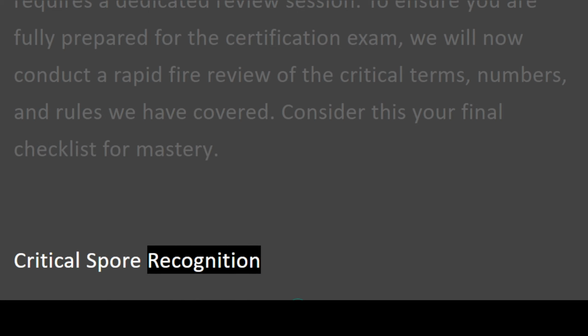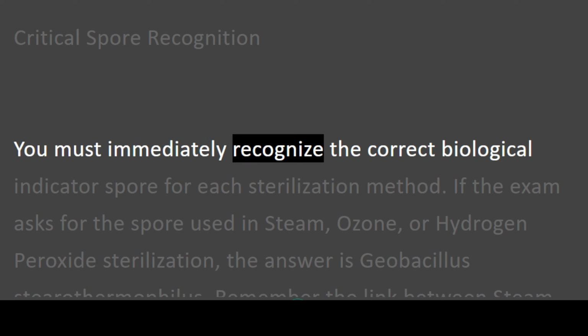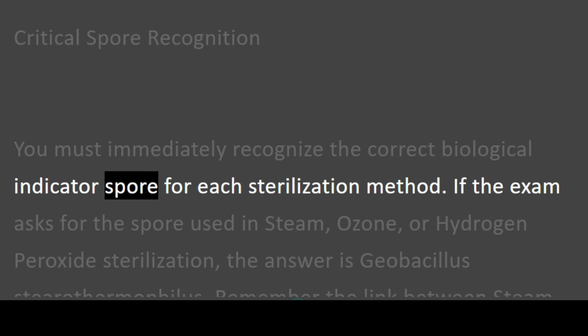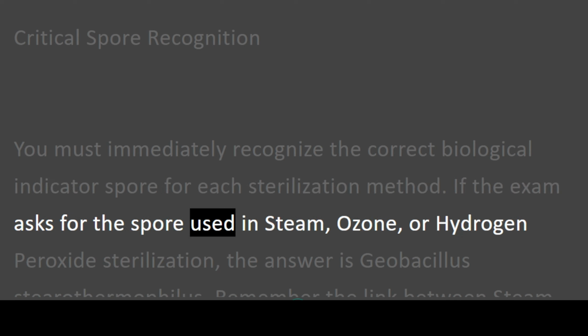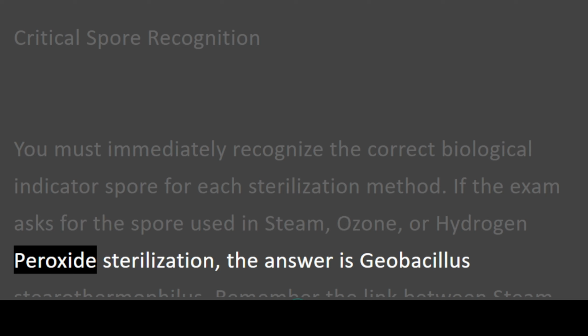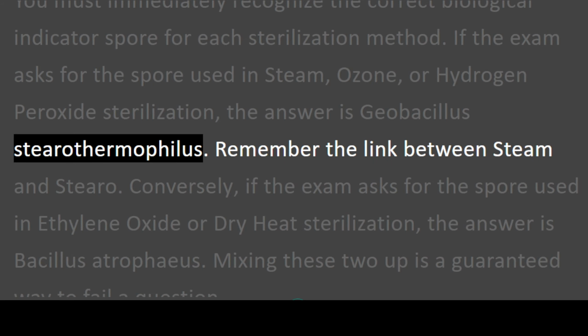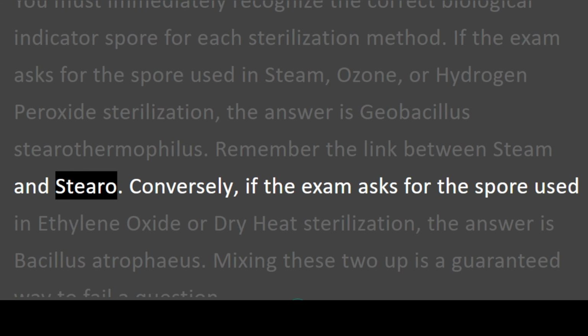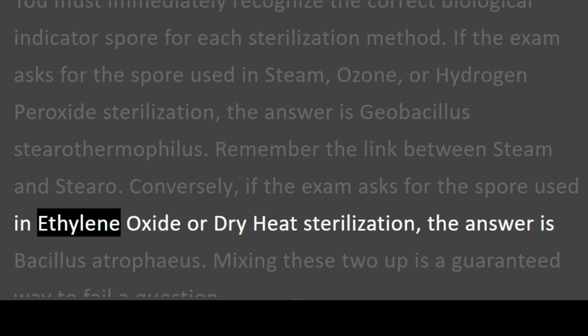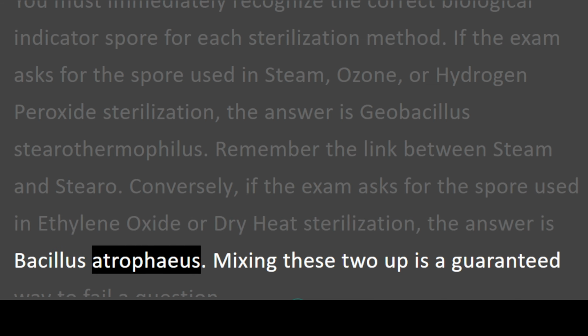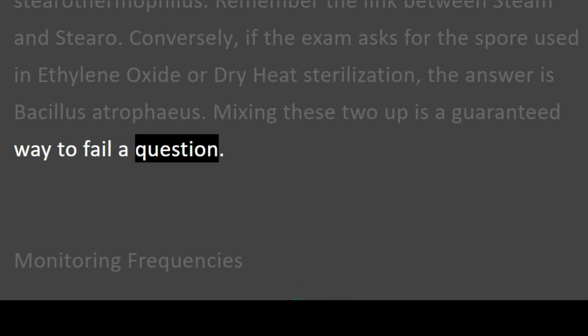Critical spore recognition. You must immediately recognize the correct biological indicator spore for each sterilization method. If the exam asks for the spore used in steam, ozone, or hydrogen peroxide sterilization, the answer is Geobacillus stearothermophilus. Remember the link between steam and stearo. Conversely, if the exam asks for the spore used in ethylene oxide or dry heat sterilization, the answer is Bacillus atrophaeus. Mixing these two up is a guaranteed way to fail a question.